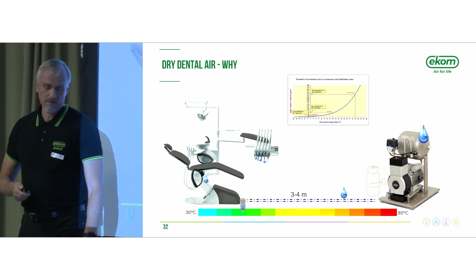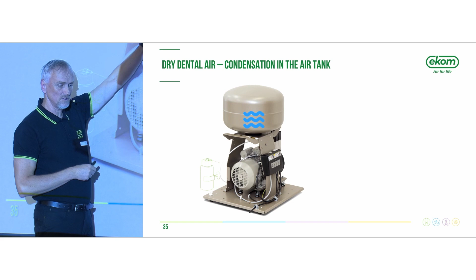All right, remember, condensation is a normal physical phenomenon. Nothing strange. It will happen with every compressor you have in the basement or in a technical room, of course, if you do not have a dryer - but I'll talk about dryers in a few slides. So if you do not have a dryer, you have to take into consideration that physical phenomenon of condensation, and you end up with water in the tank.